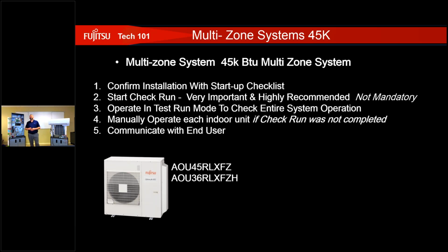All right. When we get to the 45, we want to confirm installation with the startup checklist once again. It's always going to be the same. Then we're going to start our check run. The unit's going to run in check run. That is very important and highly recommended, but not mandatory. A check run cannot be stopped unless the power is taken away from the unit via the breaker.